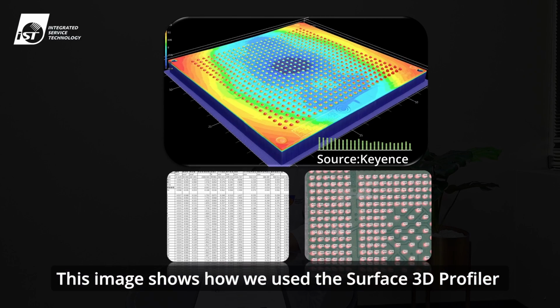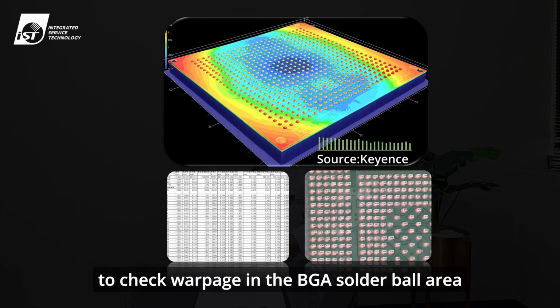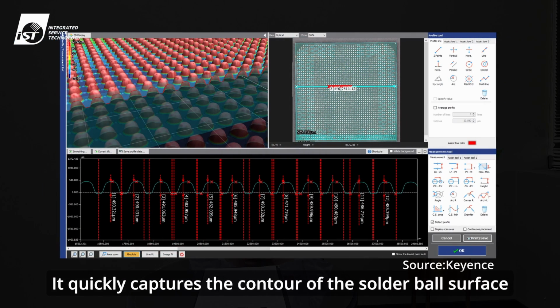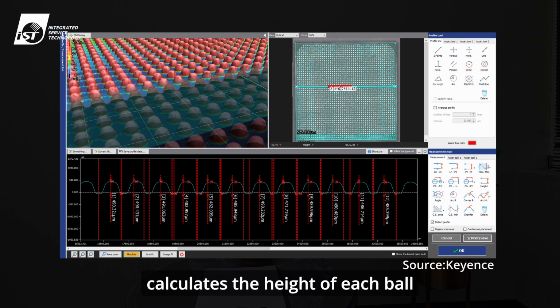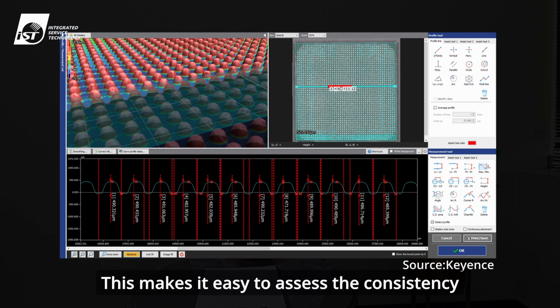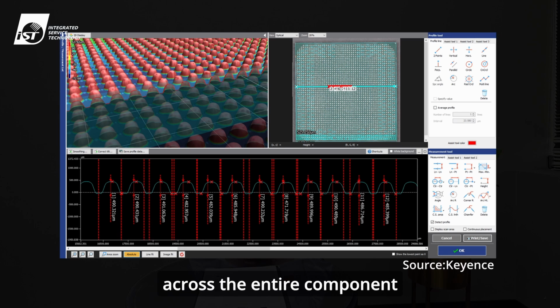This image shows how we use the Surface 3D Profiler to check warpage in the BGA solder ball area. It quickly captures the contour of the solder ball surface, calculates the height of each ball, and evaluates overall coplanarity. This makes it easy to assess the consistency across the entire component.